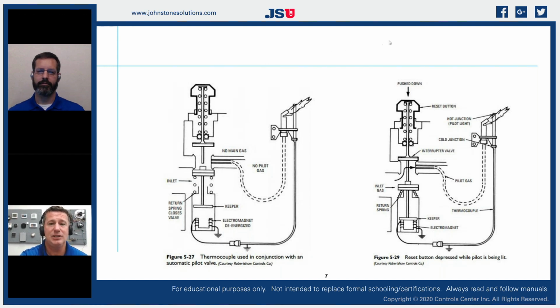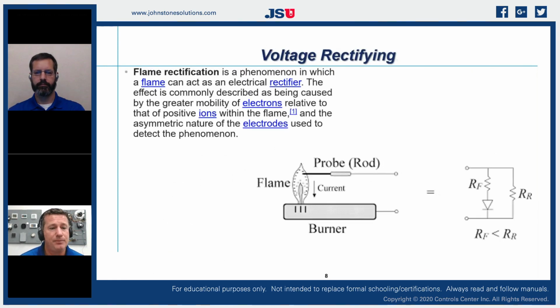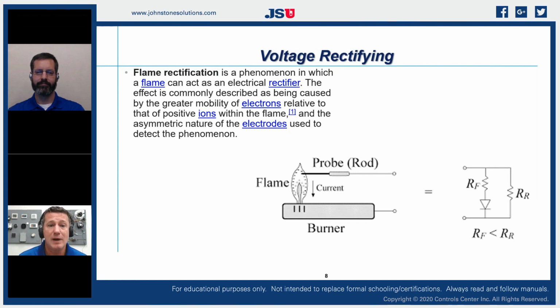Then as the equipment changed in its efficiency and as electronics developed, we moved into an entirely different platform. We moved into a platform called voltage rectifying. So we're not voltage generating anymore. We're voltage rectifying, and we're doing that through our electrical circuit, but we're using the assistance of the flame. So what was found was that as technology was moving and as electronics are developing, we could produce this phenomenon called rectification across the flame. So as a flame is burning, it has positive and negative ions across it. So it develops a path of flow for electrons, but it also can break up that flow of electrons. It can create a barrier for our electrons to flow through.